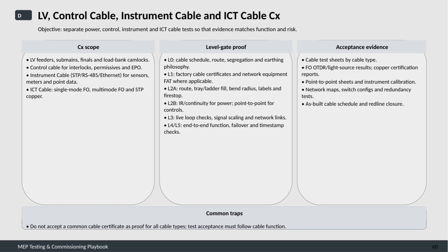For acceptance evidence, we collect detailed test sheets categorized by cable type, fiber optic test results like OTDR and light source measurements, copper cable certification reports, point-to-point test sheets, instrument calibration certificates, network topology maps, switch configurations along with redundancy tests, and the as-built cable schedule complete with redline markups for any changes.